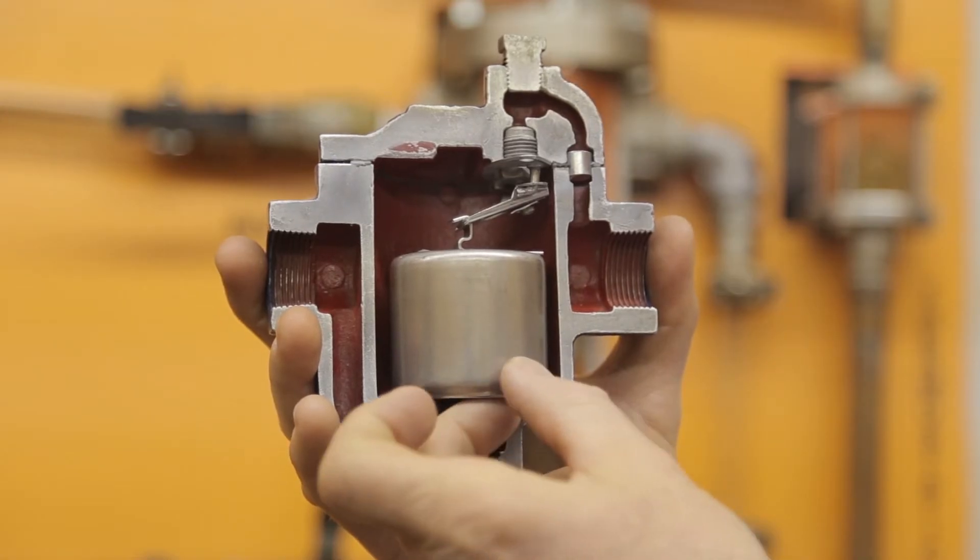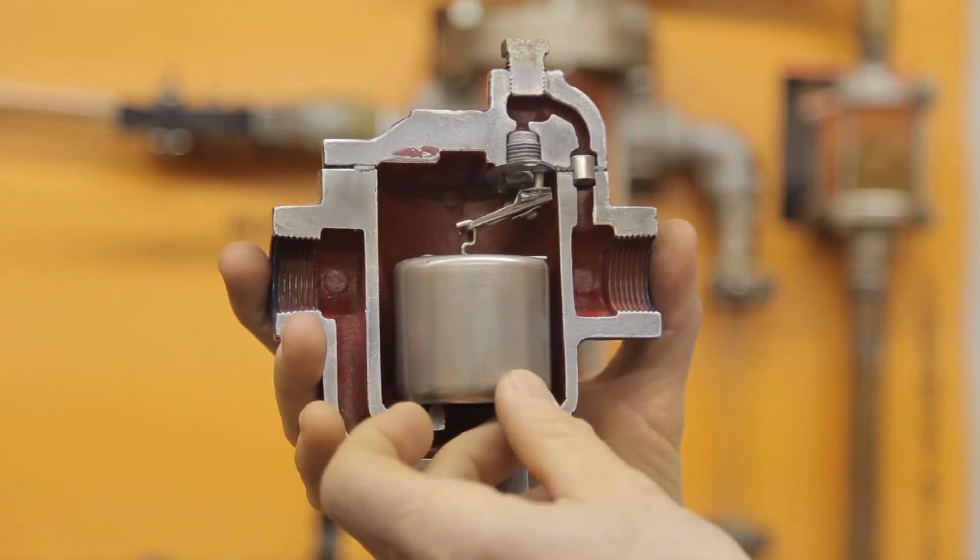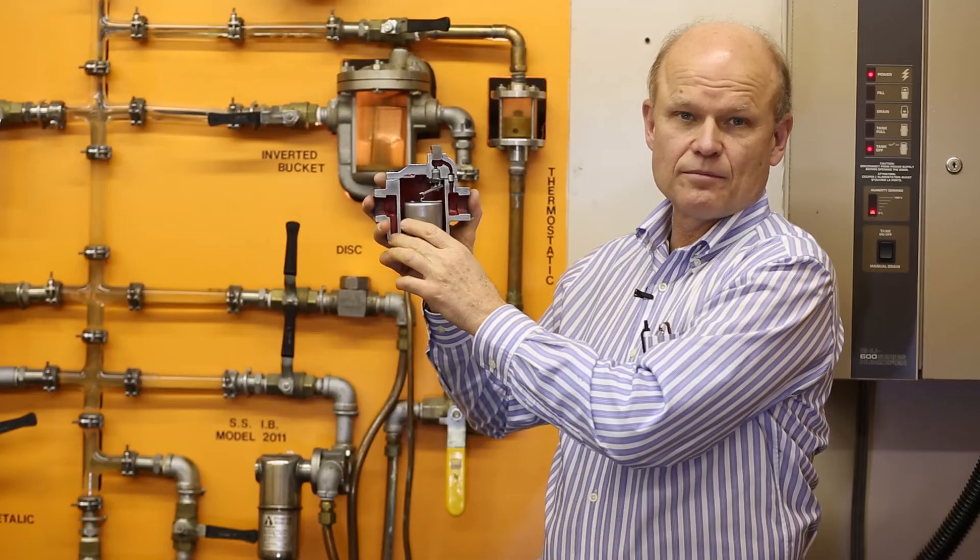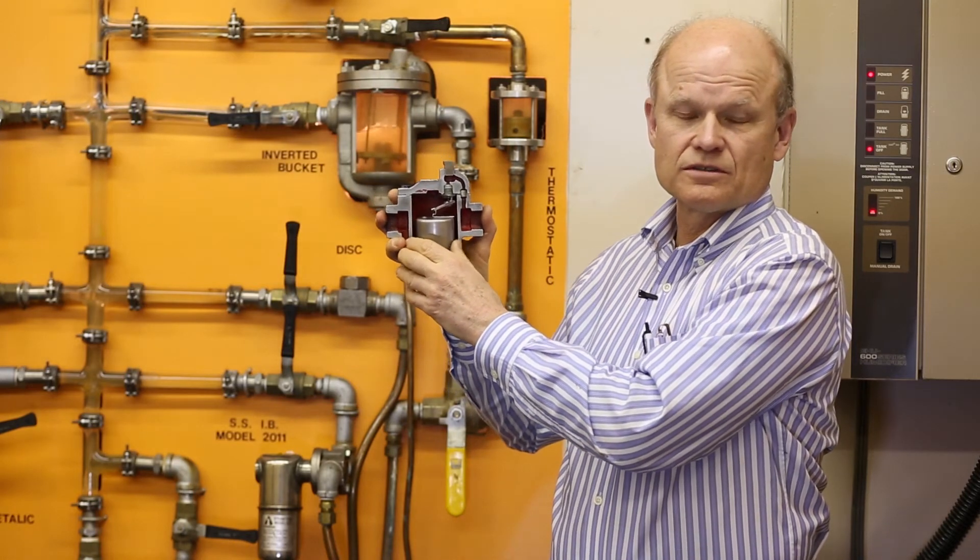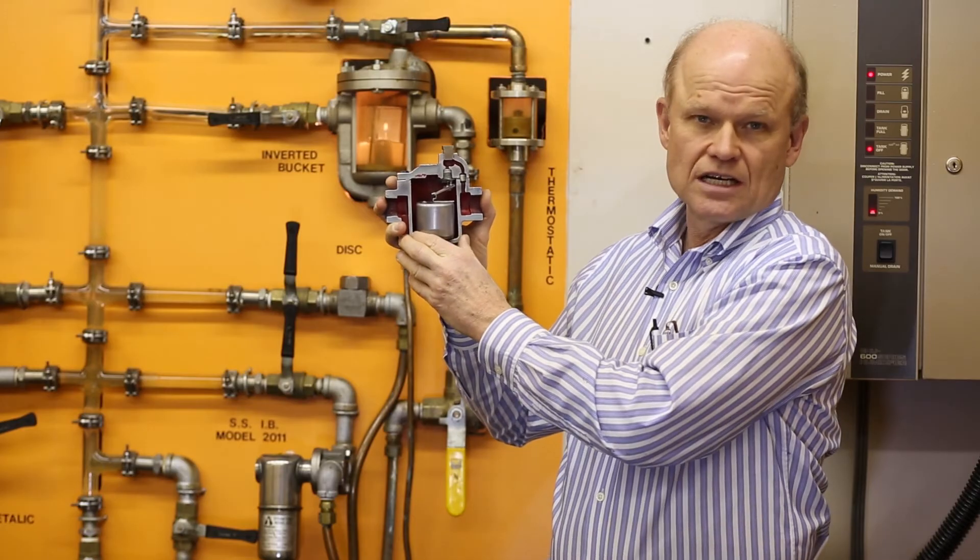This is a very durable trap design and with the outlet being at the top, it's very resistant to dirt, scale, and plugging. So this trap has a very long service life and is very durable.